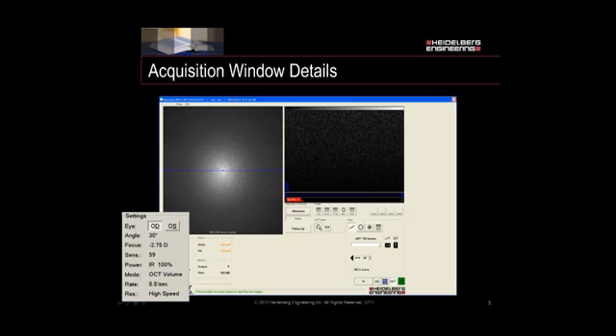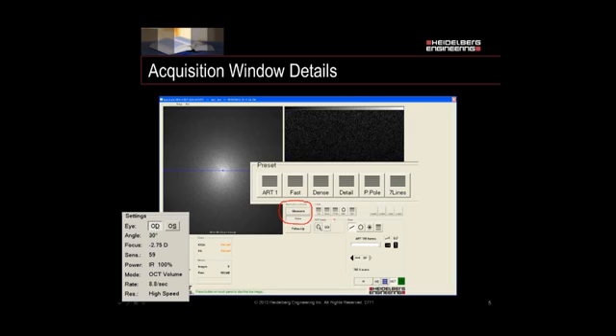Next is the structure and application section in the middle of the screen. It is currently set to glaucoma; pressing that button also gives a pull-down menu for retina. This button brings up a different set of presets for each application and structure — these presets are for glaucoma and these are for retina. Both applications will have four different custom buttons.